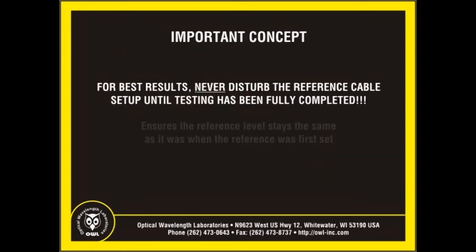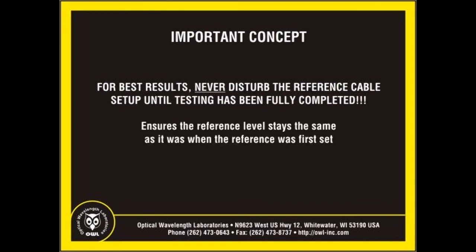Now, here's another important concept to understand. For best results, never disturb the reference cable setup until testing has been fully completed. This ensures that the reference power coming out of the light source is the same as when the reference power was recorded in the power meter.